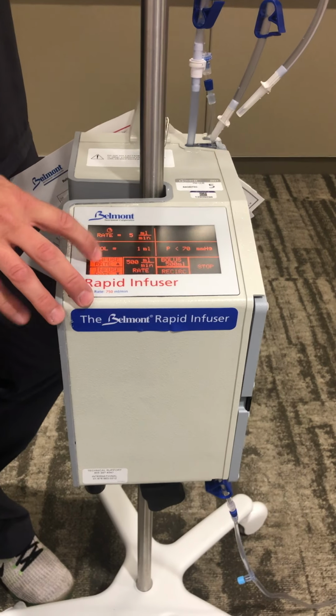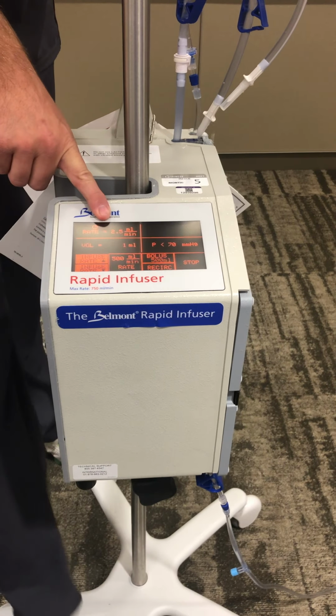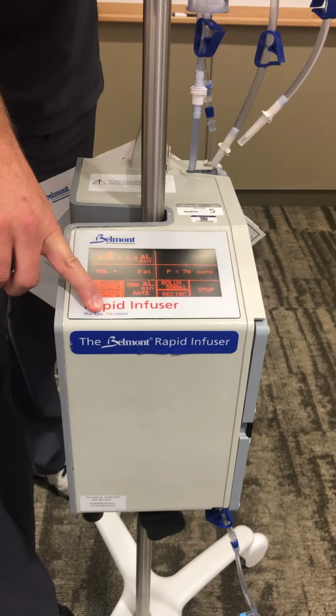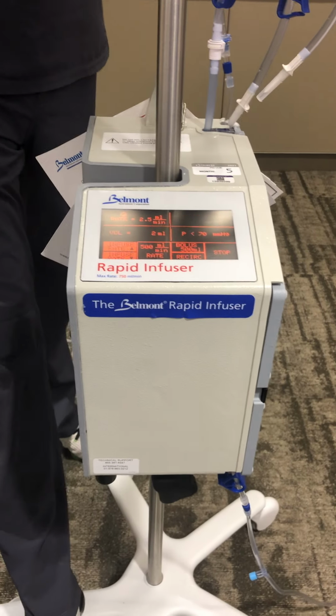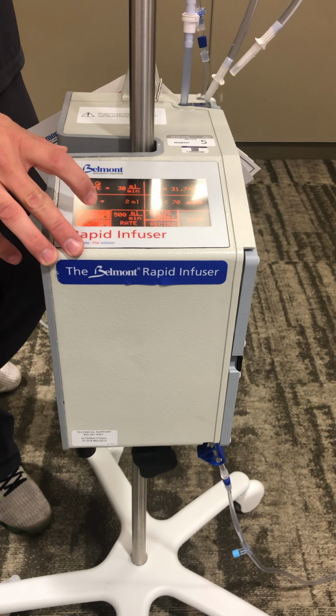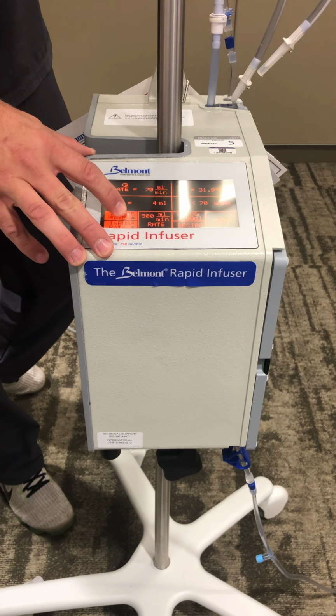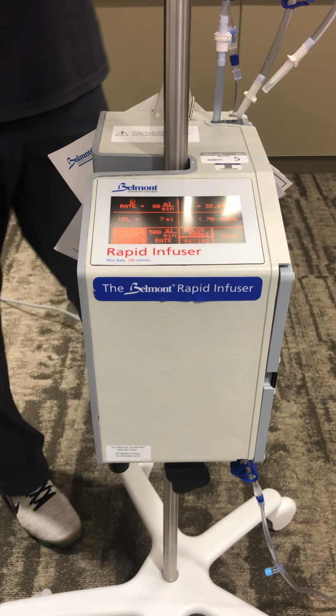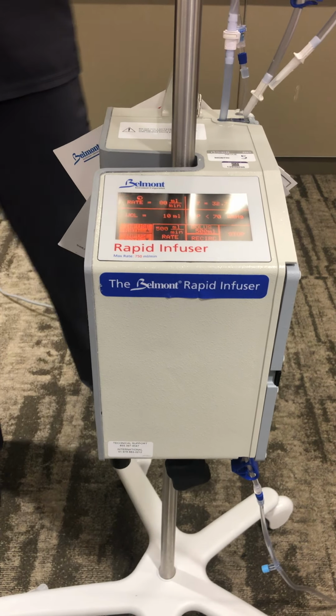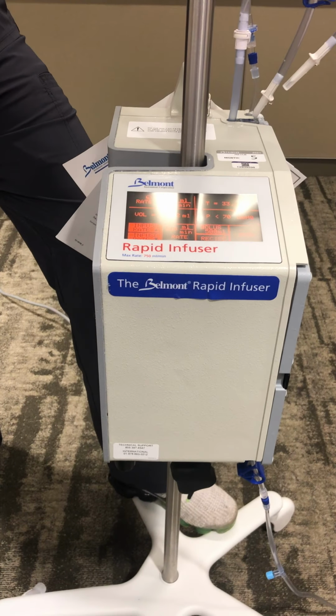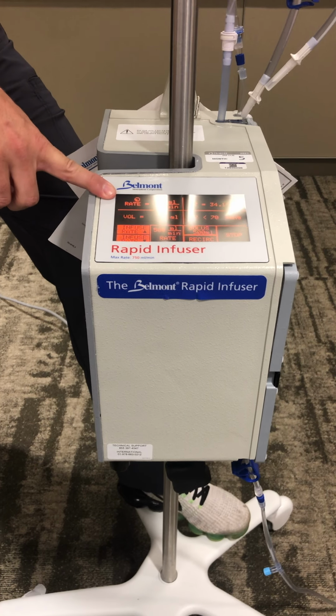So we've got our set rate right here, which can go as low as 2.5 mLs a minute, or as fast as 750 mLs a minute. Keep in mind, everything with this machine is in minutes. We can change our set rate by touching it right here. We can also press and hold and it will scroll faster. There's also a quick set 500 button that I like for a couple of scenarios, one of which I'll show in a little bit.